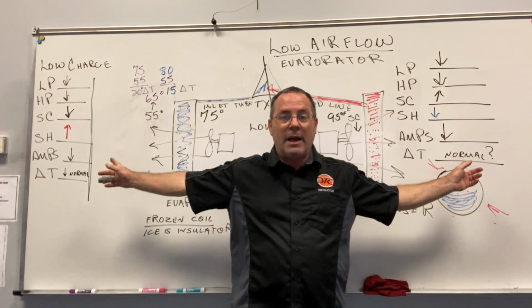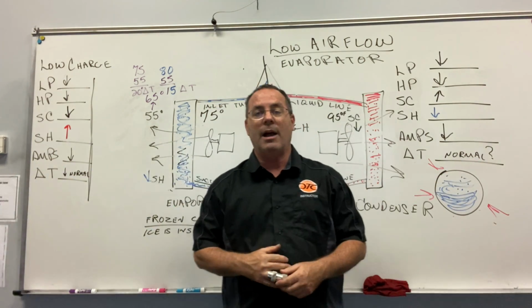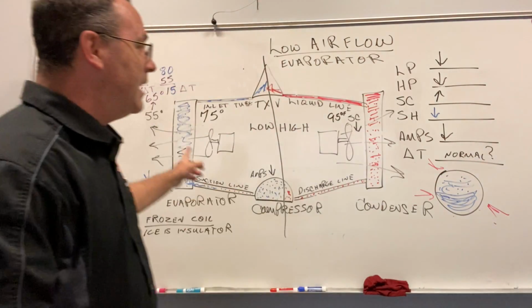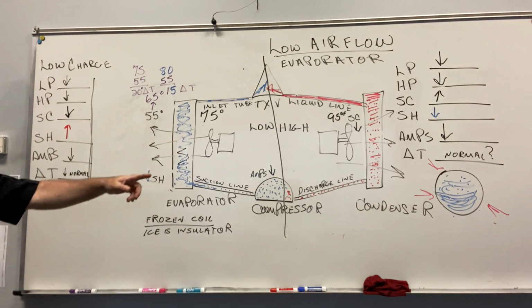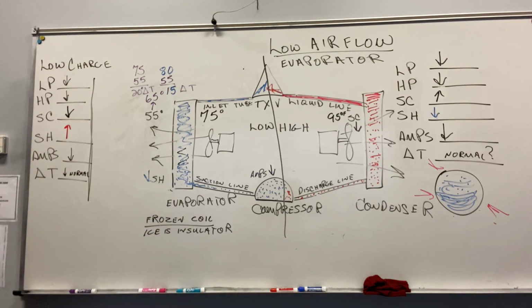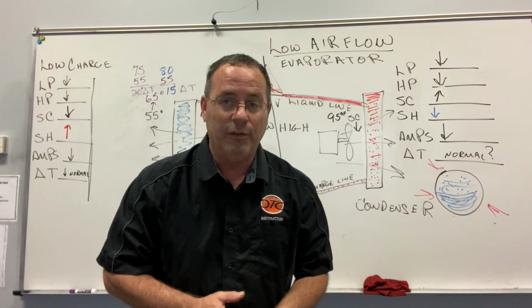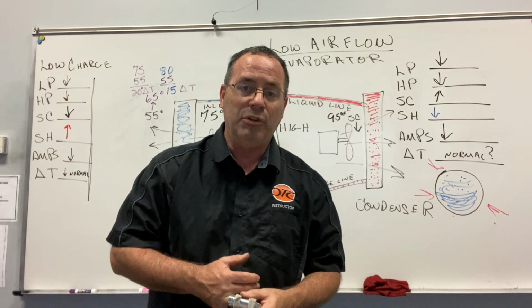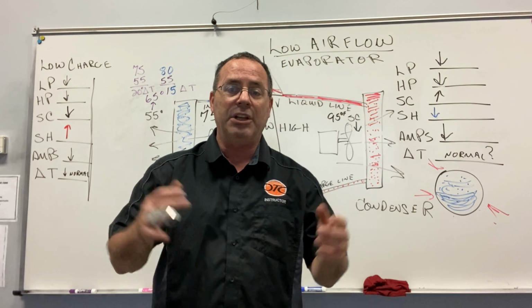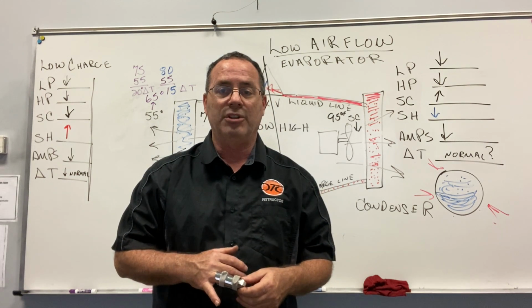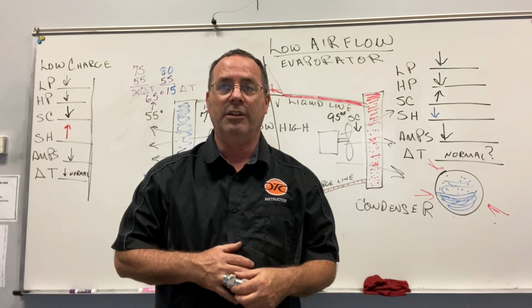You see this right here? That's what saves you time in the field, understanding this kind of technical stuff right here. This is what's going to help you understand when your coil's frozen that it just doesn't need more Freon, okay? Most people call you up. They'll say, hey, my unit's causing problems. You're like, what's wrong with it? I think it needs Freon.